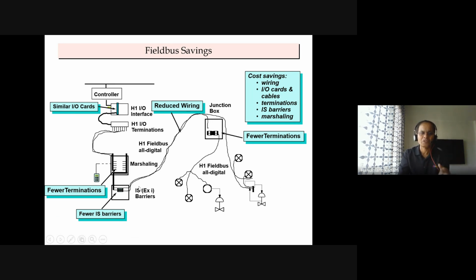Like networking, we save the wire, same thing, and you can see the size of the marshalling cabinet, size of barriers requirement, size of system IO cards, size of controller reduces. So you can see these are benefits in the field bus technology. So cards are same, but you can see fewer termination, fewer intrinsic safety barriers. Barriers are required for hazardous areas. So the requirement will be less because each cable needs one barrier.